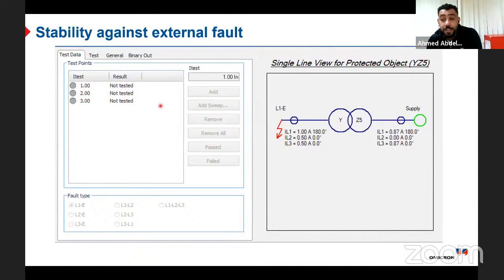The expectation is that if my system is stable, I shouldn't have any differential current. So we will say it's 0, and the bias current should be equal to the value here. And you can see here, the I test is not the differential current. The I test here is the bias current, because I'm simulating a stable condition, and in a stable condition no differential current should flow, because my system should remain stable.